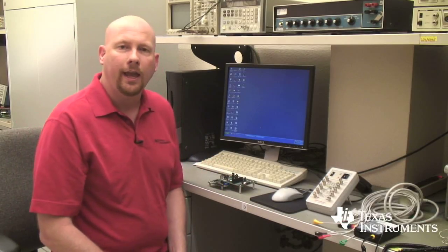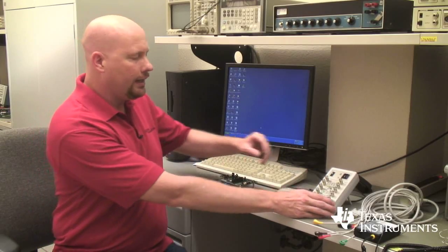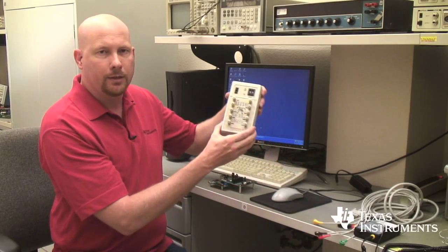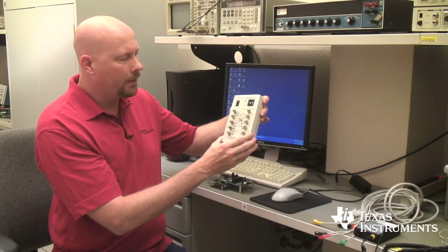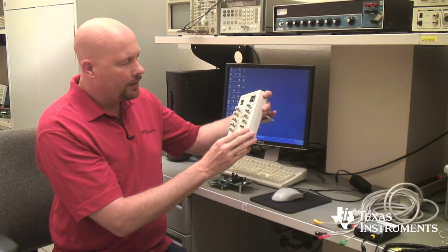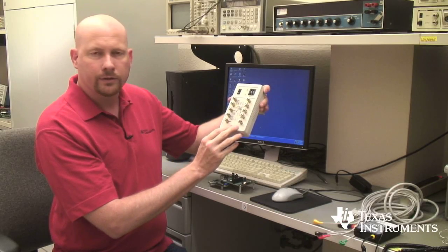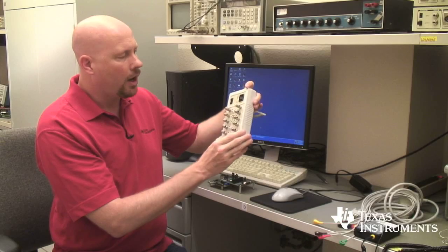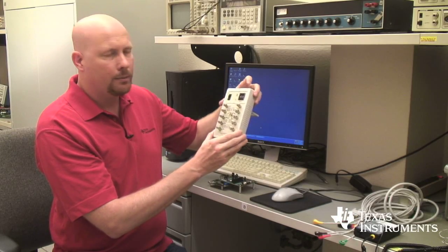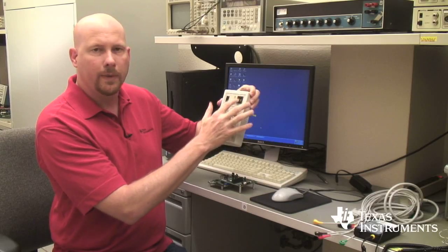Now to evaluate the ADS1298 with ECG type signals you'll need an ECG signal simulator such as this one. This is a fairly inexpensive model. It has all of the common ECG connections in snap connectors that are all very clearly labeled and you can adjust the heart rate and simulate different kinds of cardiac conditions using these buttons at the top.